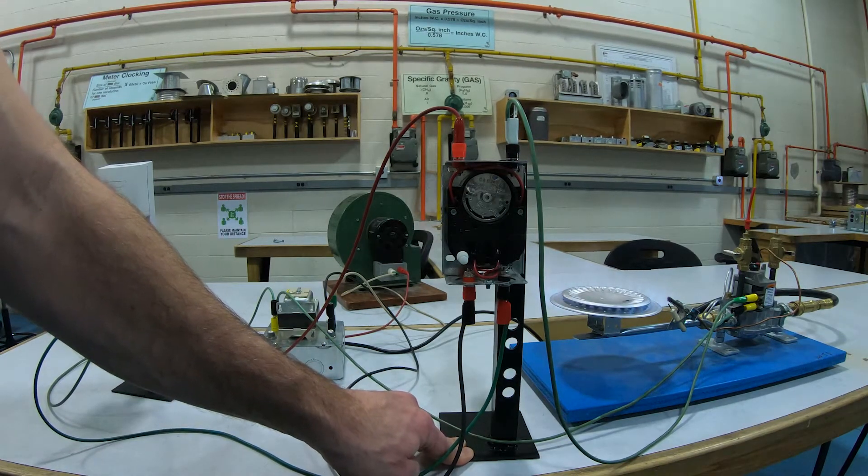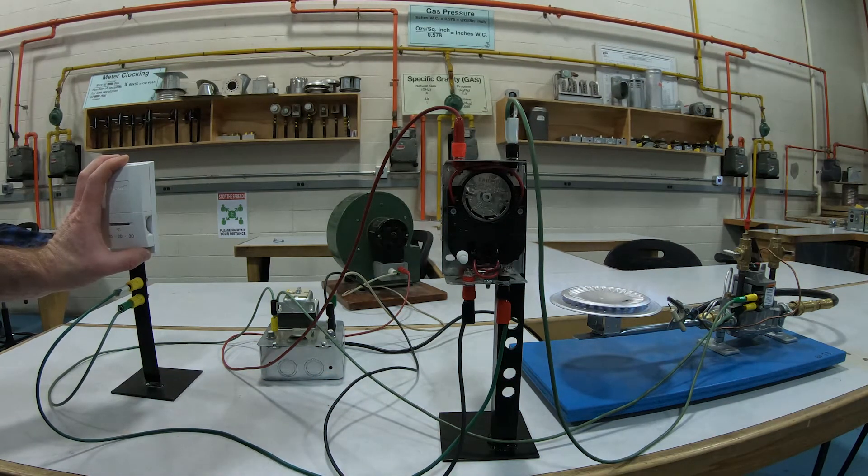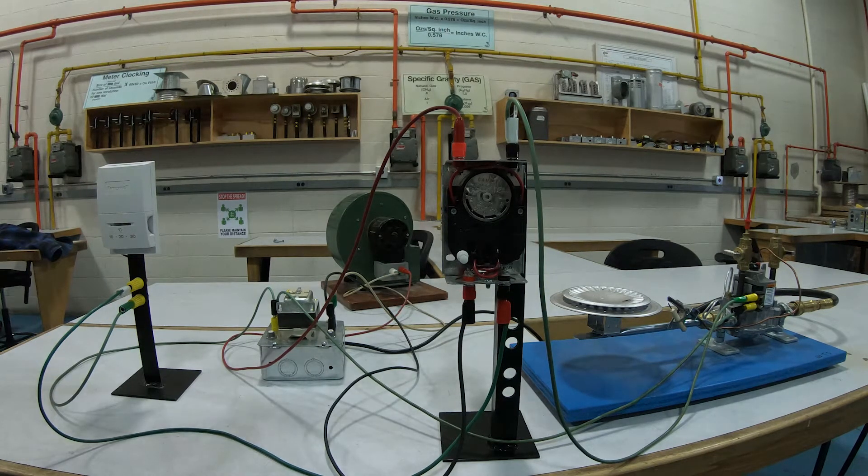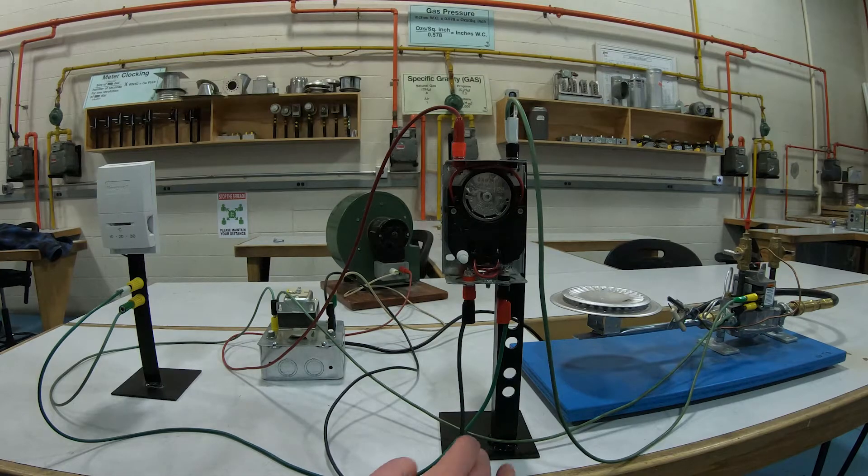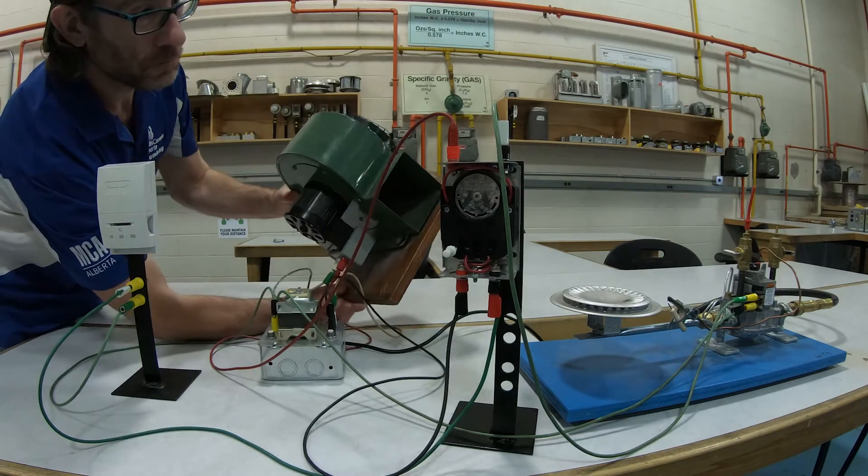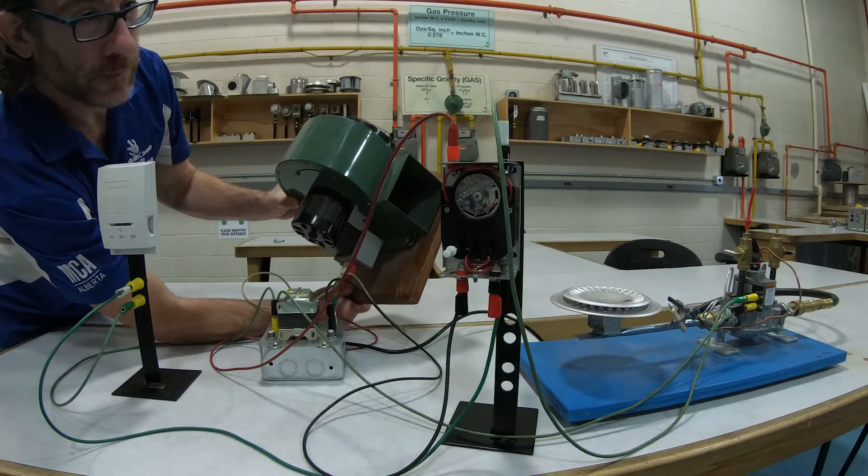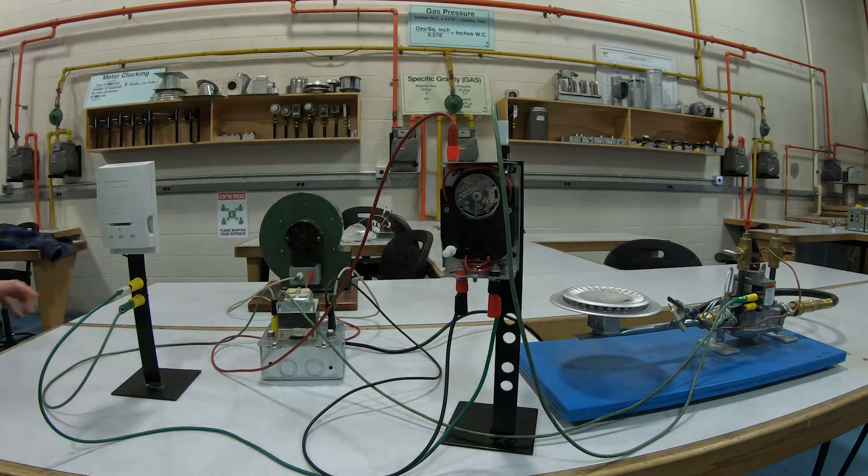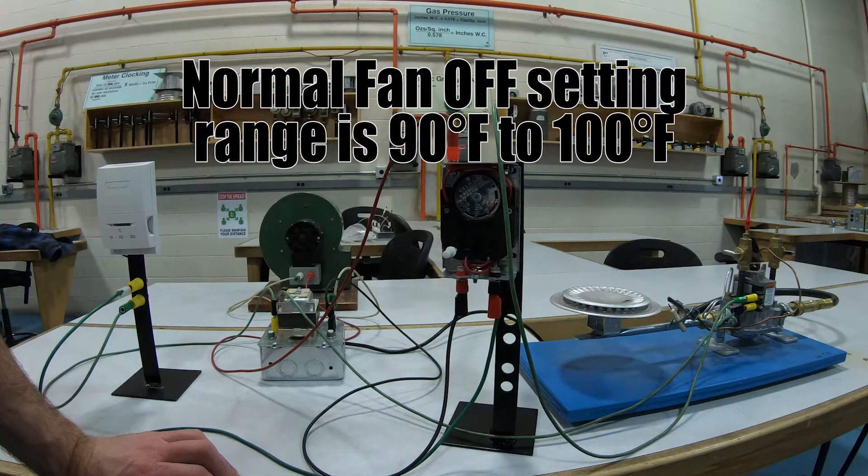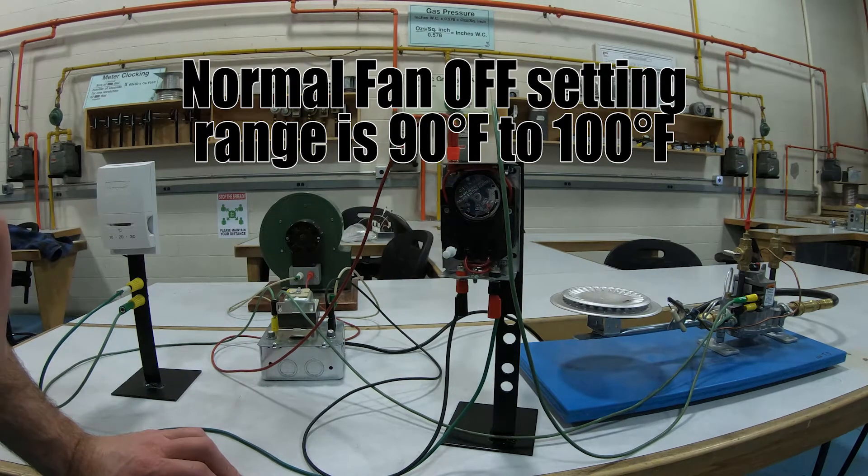Now I'm not going to stick it back in the flame, but what we're going to do is turn our thermostat off, pretend that the furnace or house has been satisfied for heat. And now just to speed things up a little bit, I'm going to use my fan to cool this down because I can. There we go, I cooled down to my fan off temperature, and now we shut down. Fan off temperature is generally between 90 and 100 degrees Fahrenheit.